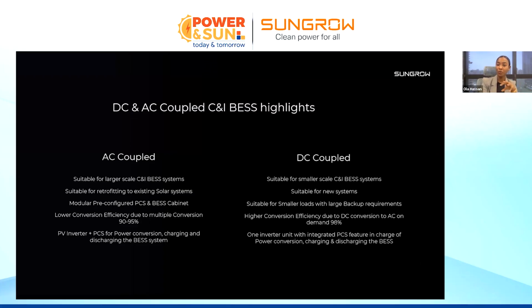It's suitable also for smaller loads with large backup requirements, because with the AC coupled, the PCS capacity is not changed. It's 125 kilowatt and the battery can be 257 or 510. If we need bigger battery capacity, then we're adding another model. So with adding the model with batteries, we are also adding PCS, power conversion systems, as well. So that's why it's suitable for larger scale. But if my load is small and my energy storage capacity requirement is big, then the DC coupled is better, because one inverter has a rated output, for example, 125, but we can add to the battery capacity, all right? Because one inverter unit has the PCS capability inside, and then we can add on the battery side, because the battery side does not include the PCS, it's built inside the inverter. So we have more flexibility in adding bigger energy storage capacity without adding more PCS capacity.